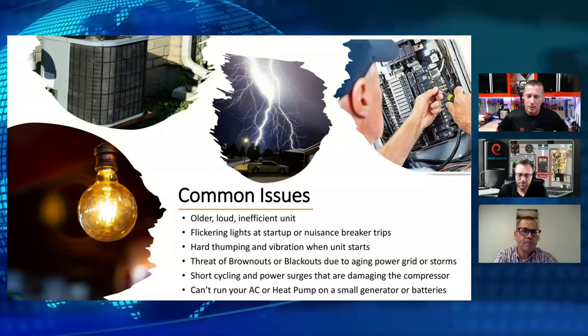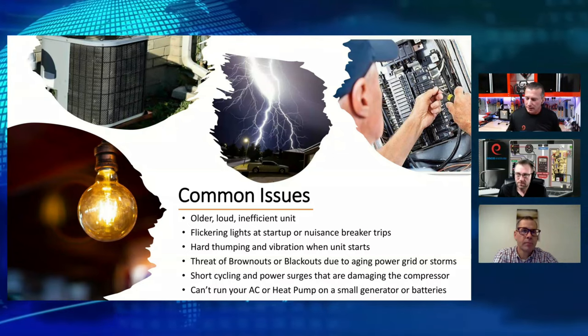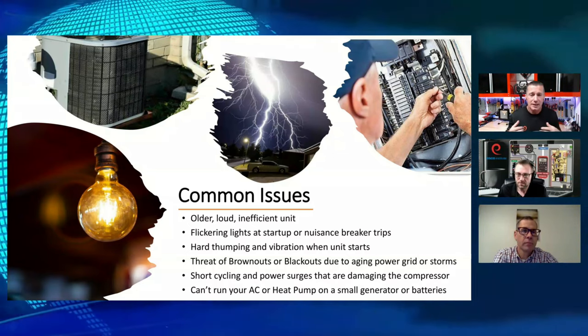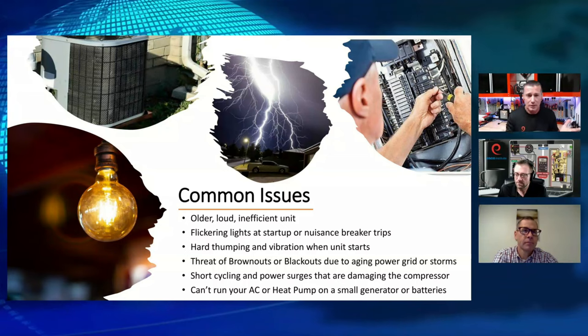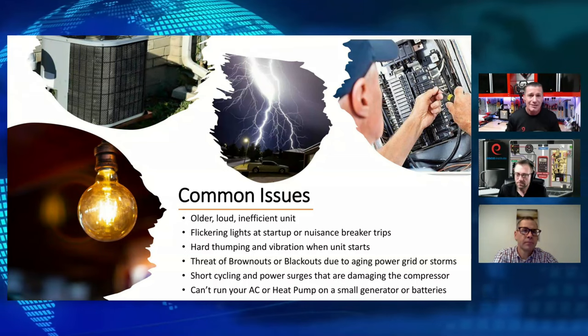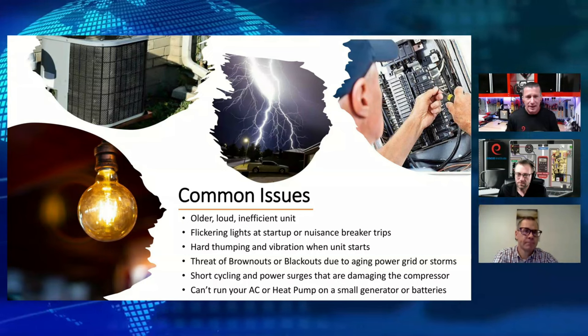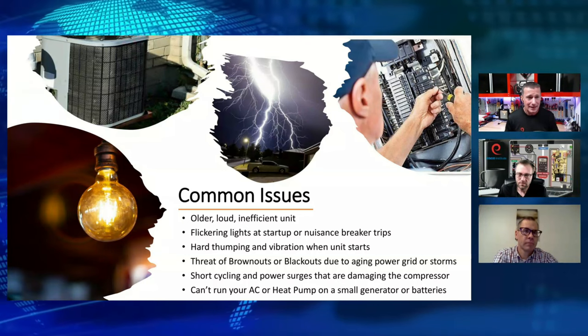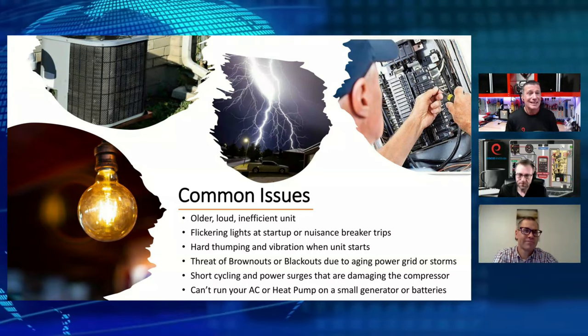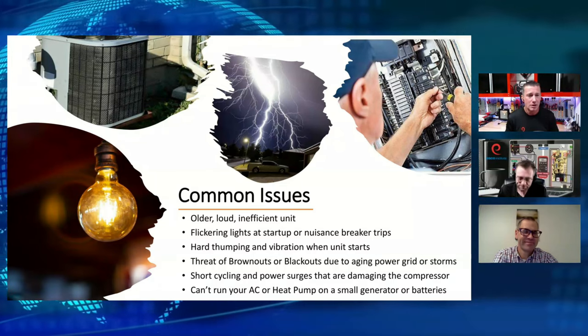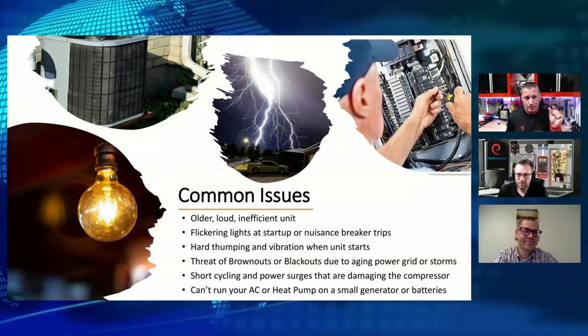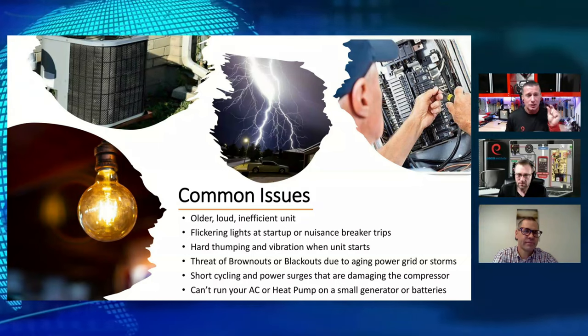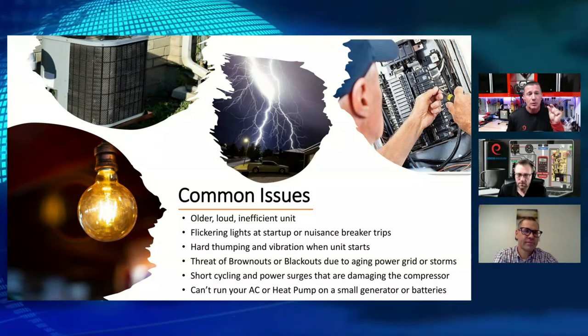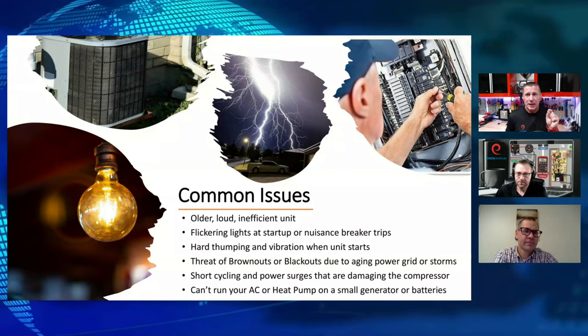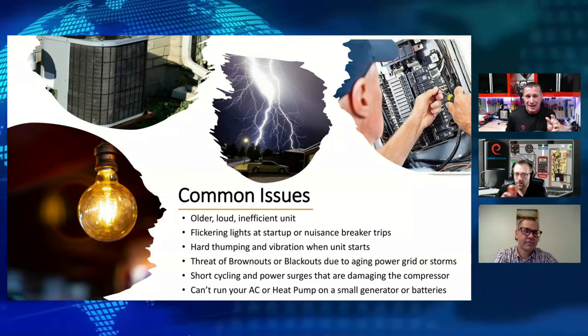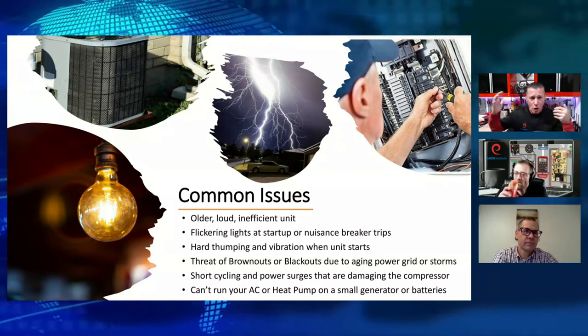When we think about loads on generators, you could look at a system that has a current rating, like mine, with a run amperage of around 8.8 amps. That's fine and dandy if I have a source to supply 8.8 amps, but how am I going to get it turning when I need 47 amps just for startup, only for a short period of time? That's where it comes into play with generators or battery sources, where systems designed for backup are not necessarily rated for those large inrushes of current.